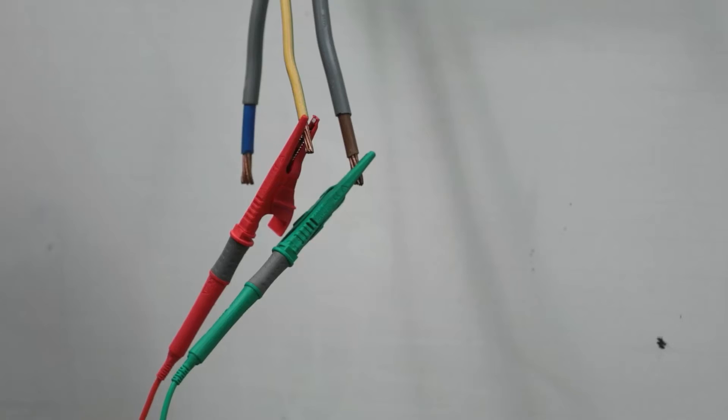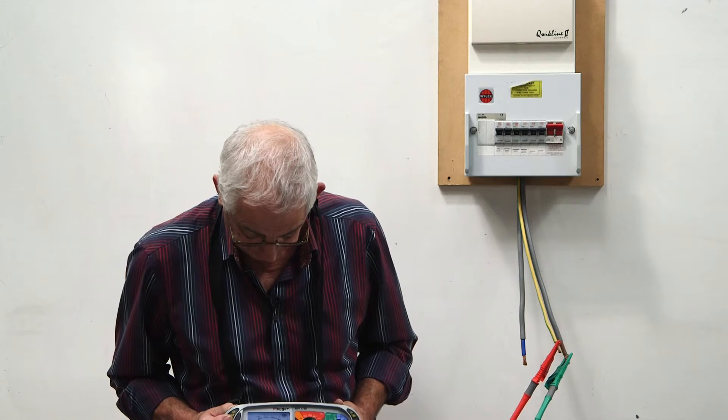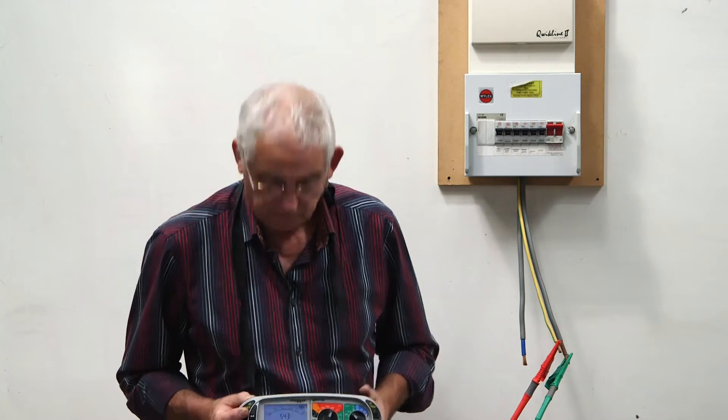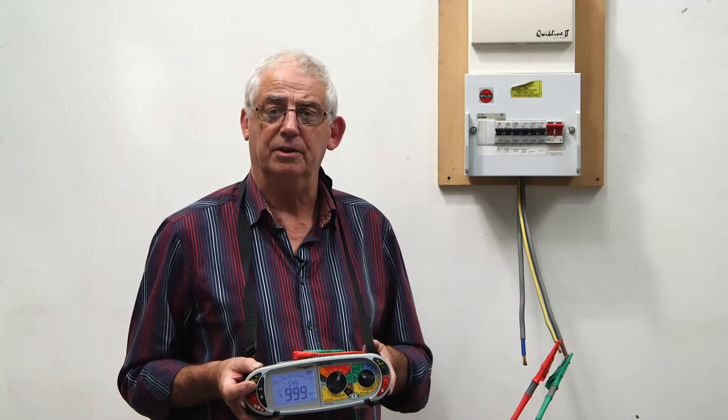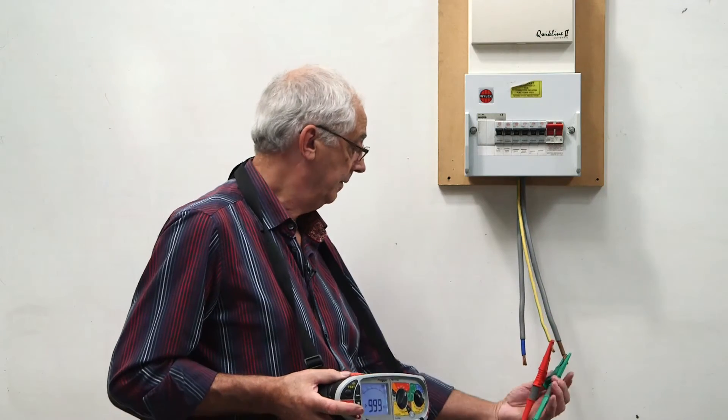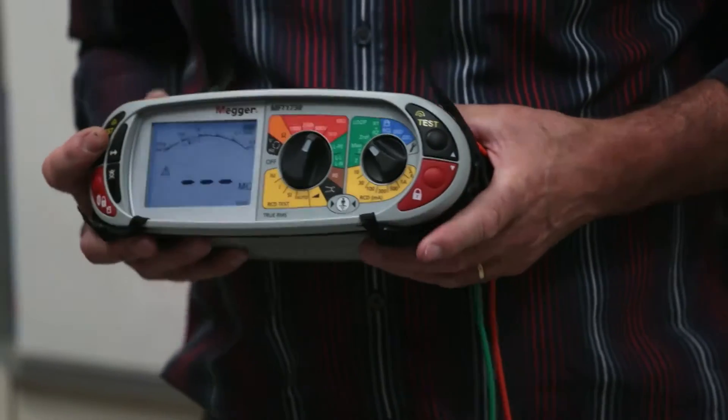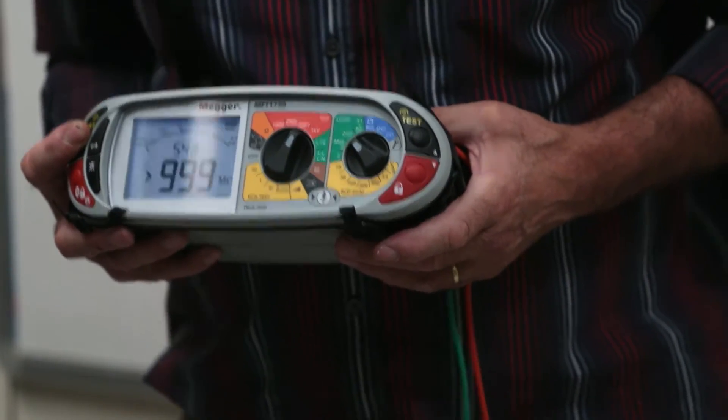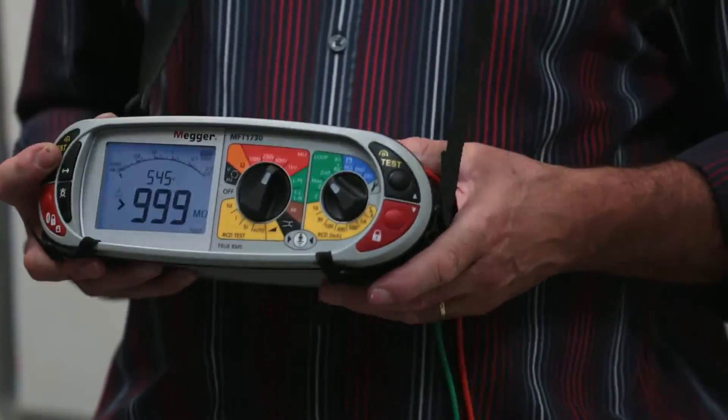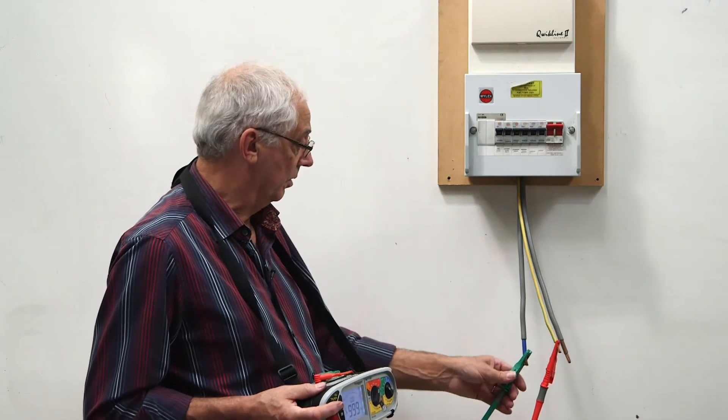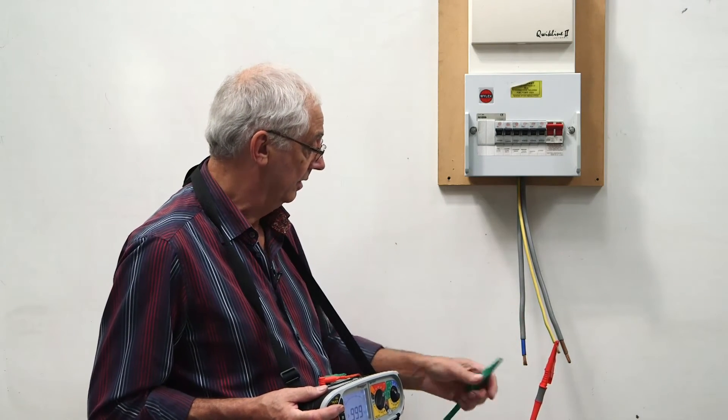So line to earth now. Greater than 999, so I know that's okay. I know that my fault lies between line and neutral.